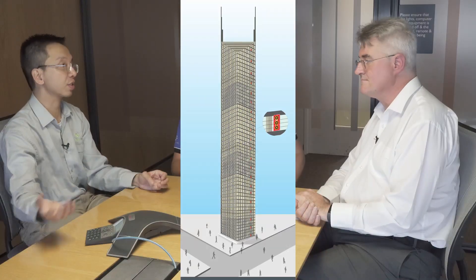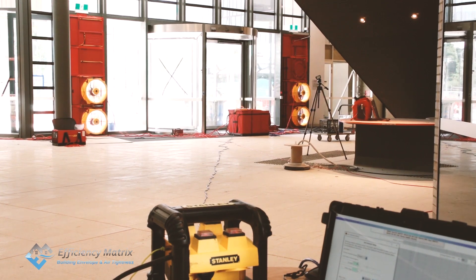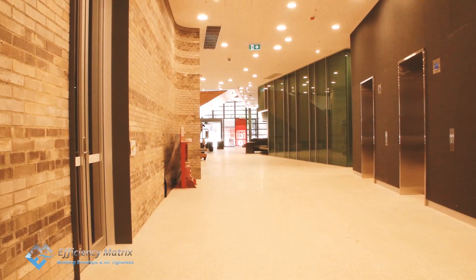For example, on a 35-story commercial building, we would set up fans on the roof level to pump into the stairwell, and then at the intermediate plant room level to also draw air in from the ambient, and then at the ground and potentially the basement level if there is an open ventilated car park. We can get air from different points and distribute it evenly to reduce the pathway that air needs to travel through. That's the best way to test because it won't have any internal leakage through areas that are not supposed to be airtight.